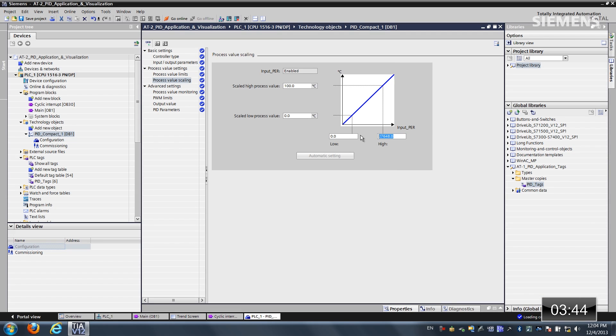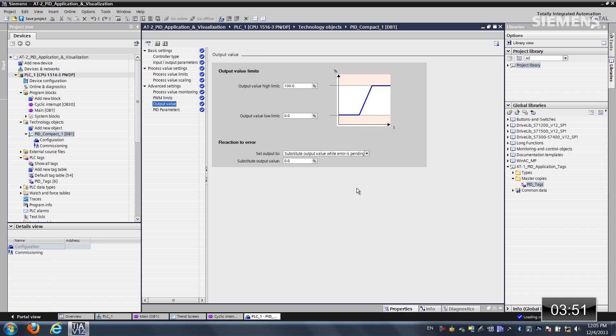and I'm going to change this high to 1,000. And last but not least, on the output value, we also have something reaction to error for this new version 2 PID compact. We can do a substitute value or whatever the last known value is. That way, if there's an error, it just maintains steady operation mode.